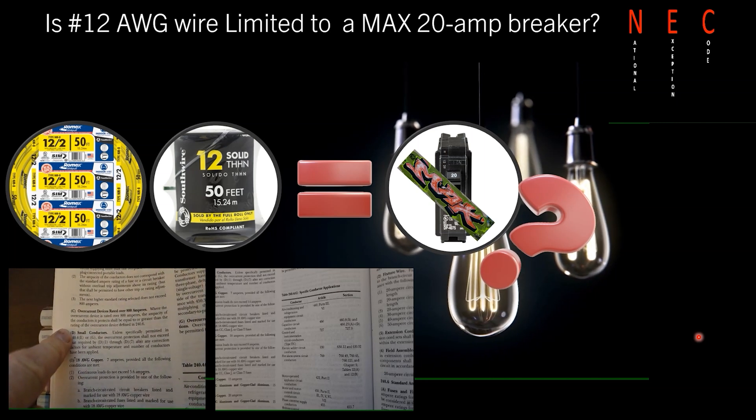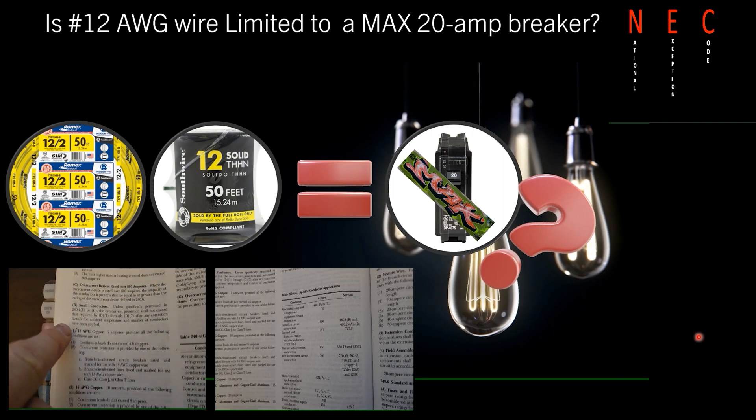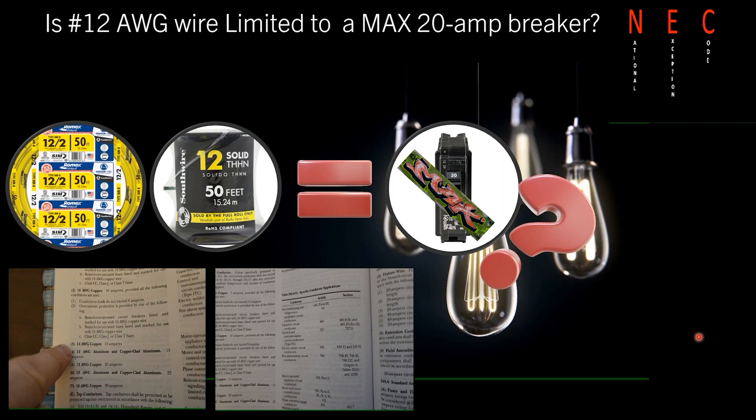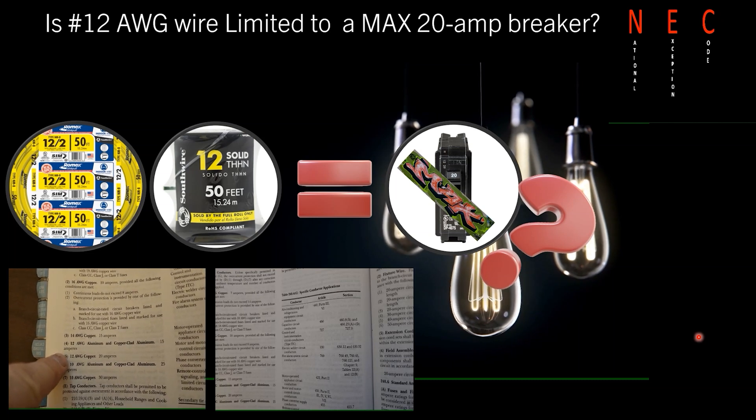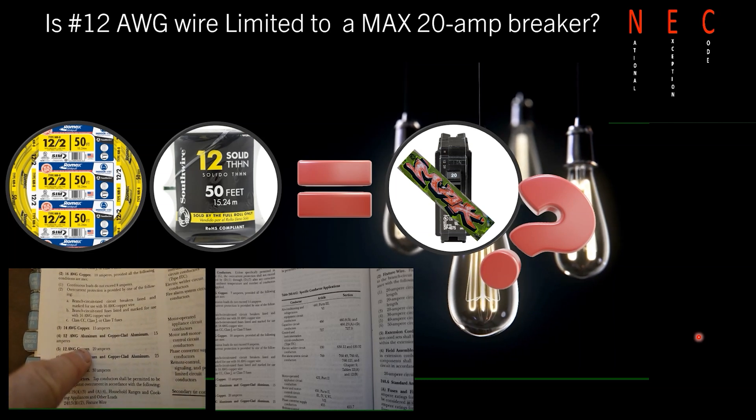But if it's not listed in part E, which is tap conductors, or in part G, you are not allowed to exceed 14 gauge wire on a 15 amp breaker, 12 gauge wire on a 20 amp breaker, and 10 gauge wire on a 30 amp breaker.